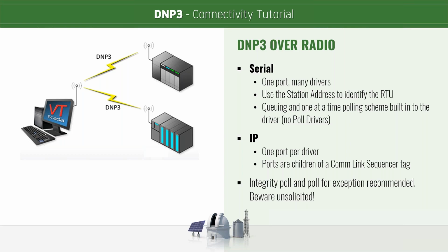There's tons of radio systems that tell you that they can support that sort of thing, and maybe they will. But our general experience is that with radio it is very important to keep the master in charge, and very important to not have the outstations deciding that it's their time to go and sending stuff in and interfering, because it can really degrade your communication channel and take out other more important data that might be going through it.